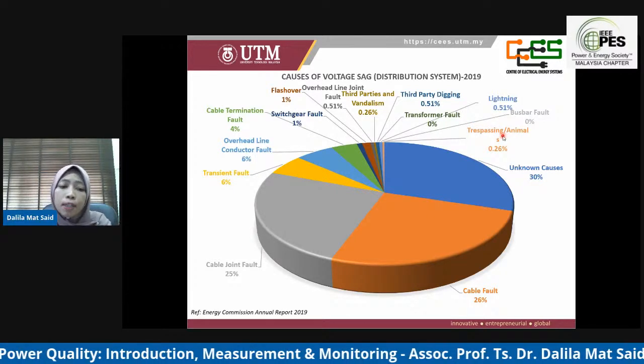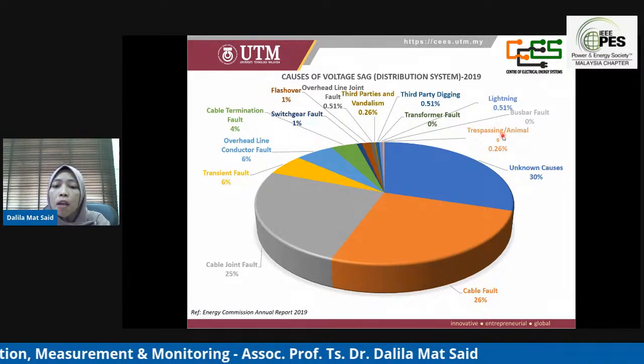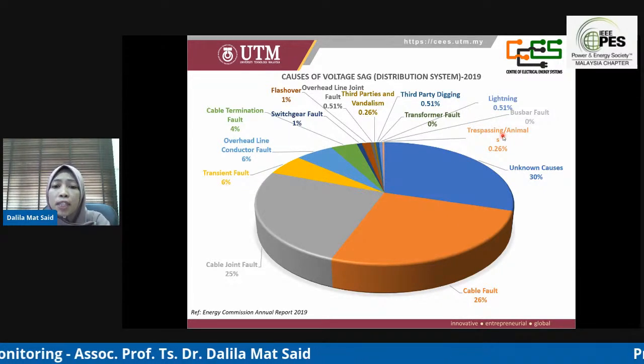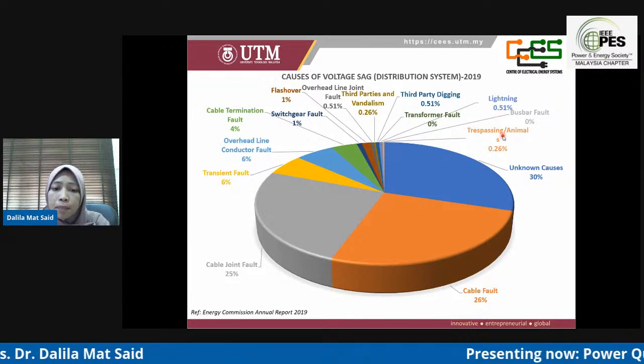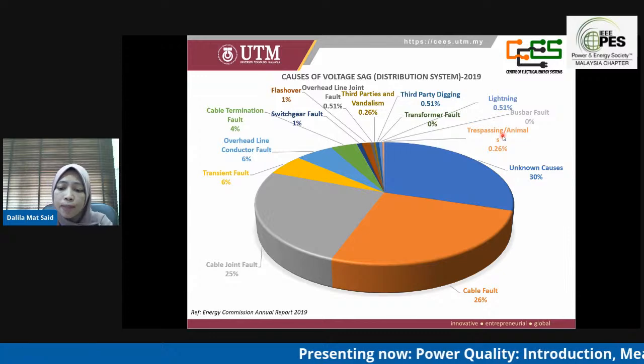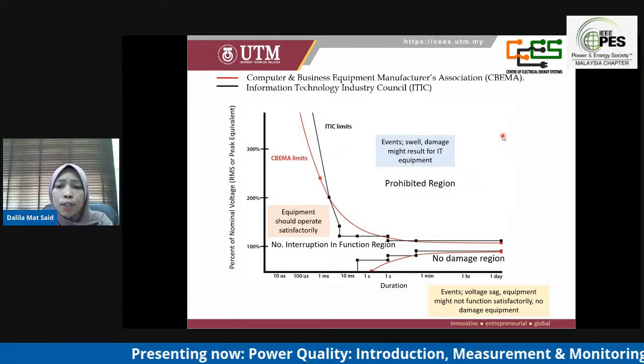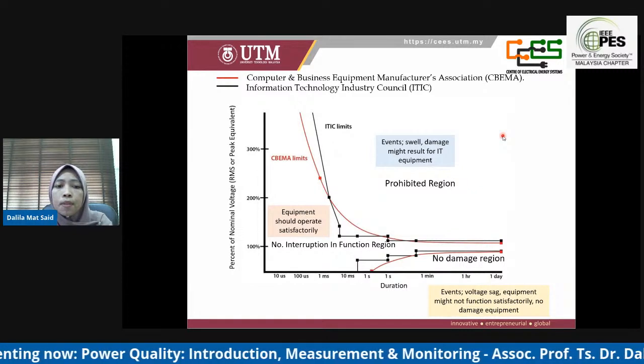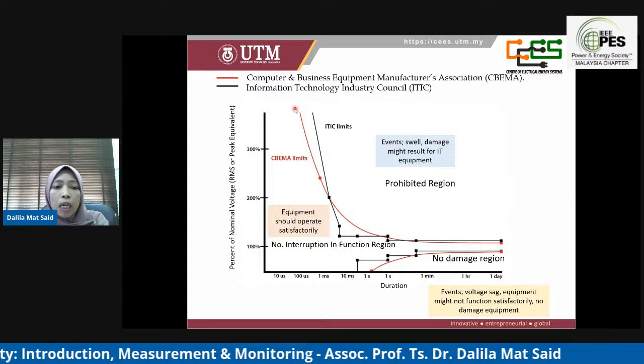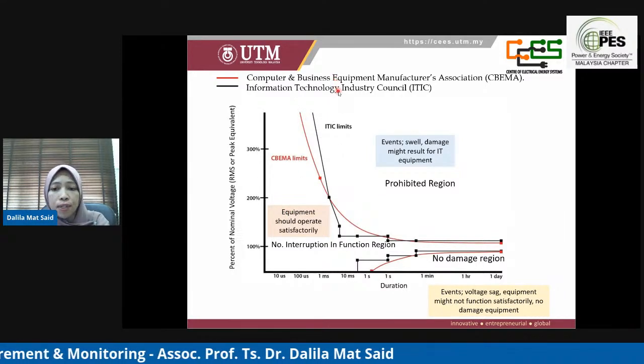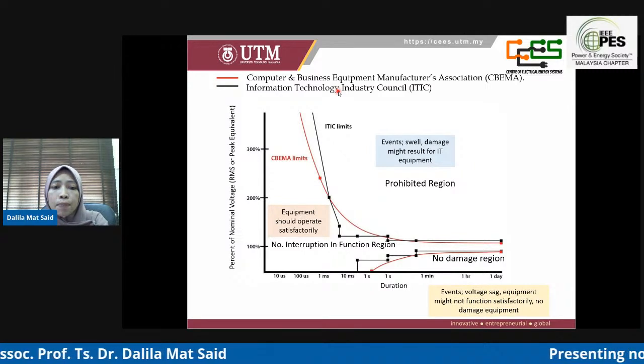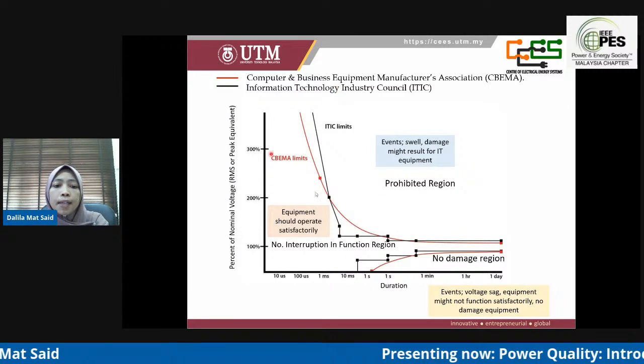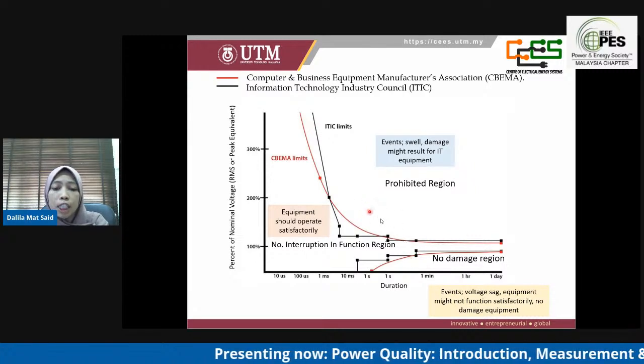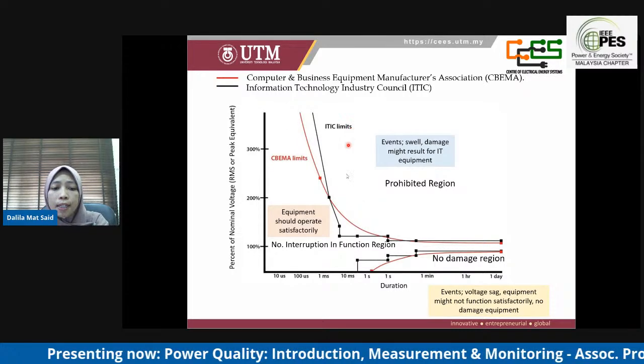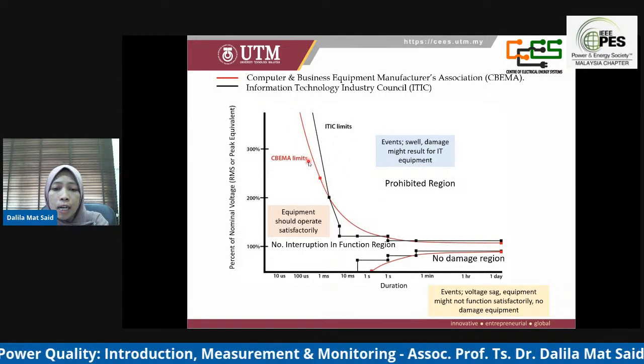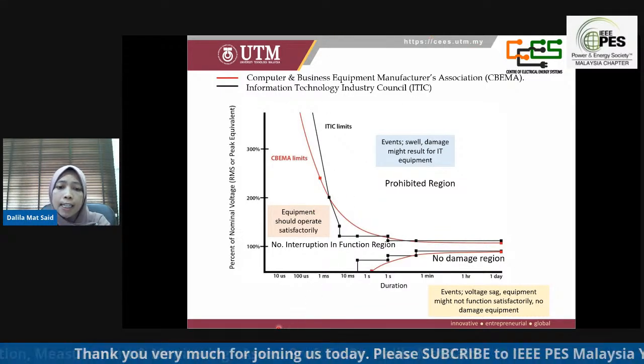So based on the event, in order to investigate the impact, we can refer to the immunity levels provided, such as in the CBEMA, ITIC, IEC, and SEMI F47. Next we refer to this curve. This is the Computer Business Equipment Manufacturers Association curve, published in IEEE Standard 446. It is intended to illustrate the suggested computer susceptibility lines. The red line indicates the CBEMA curve, and the black line indicates the ITIC curve.